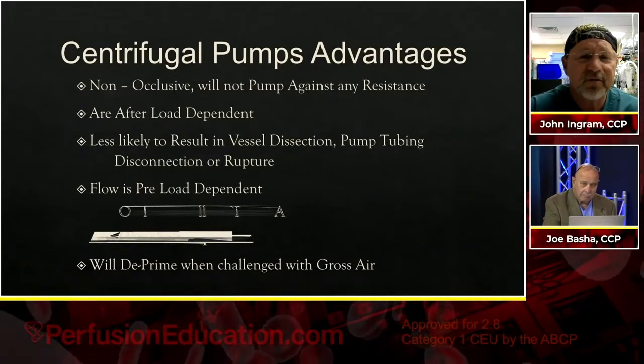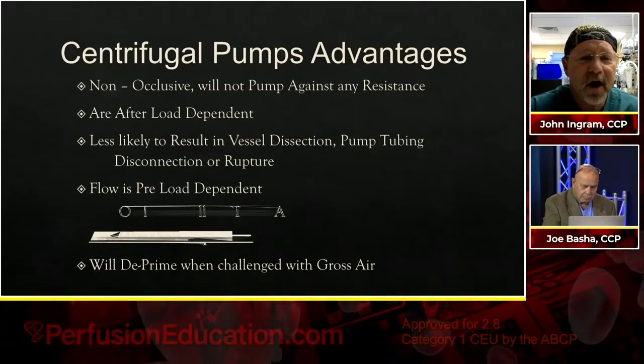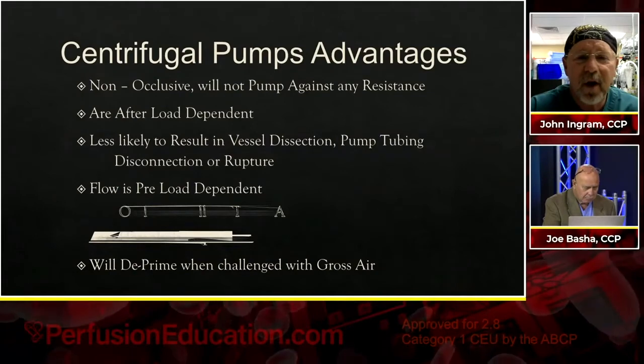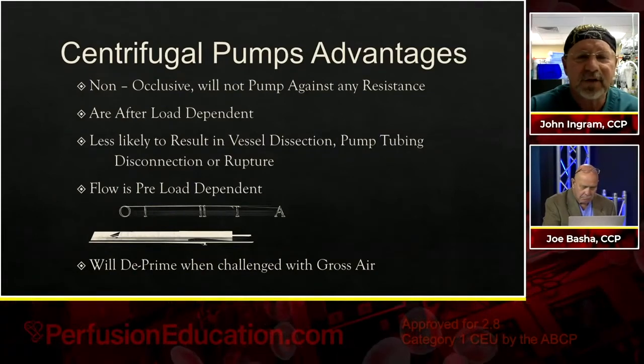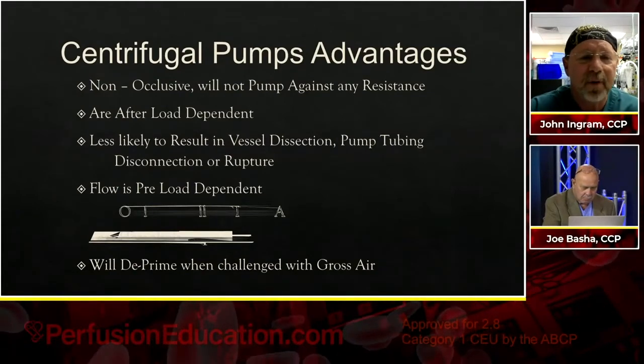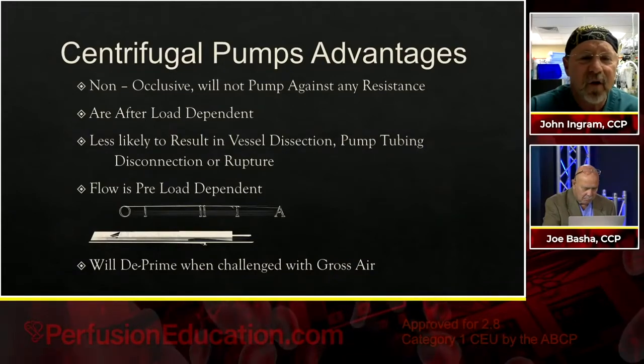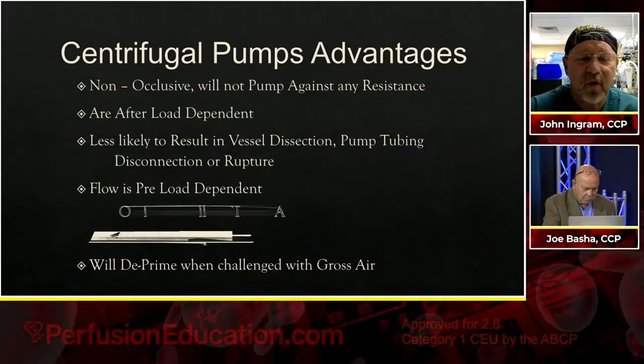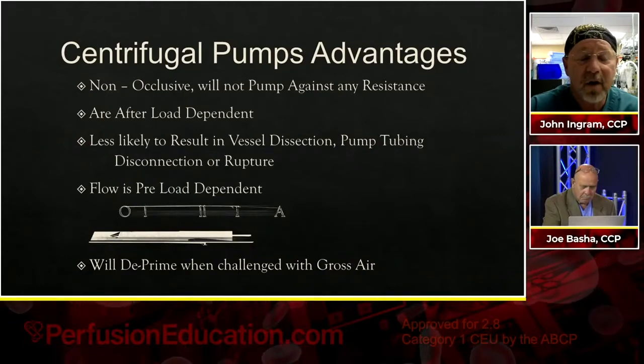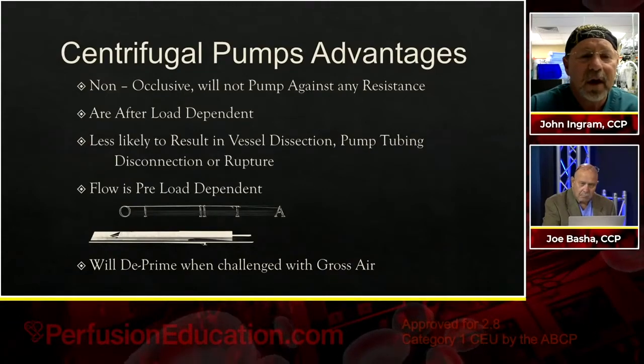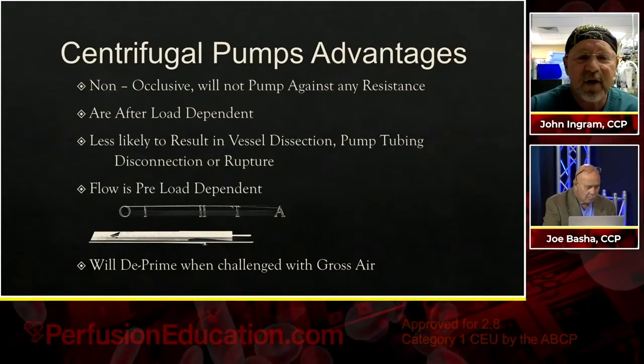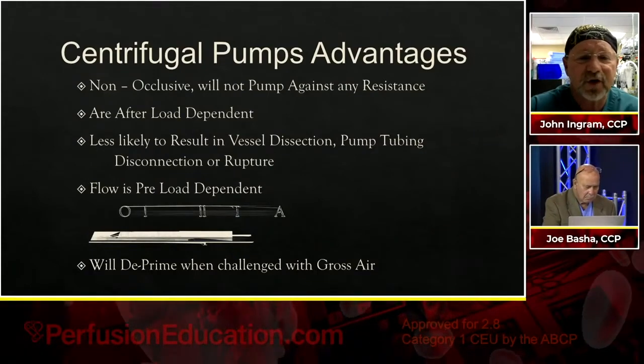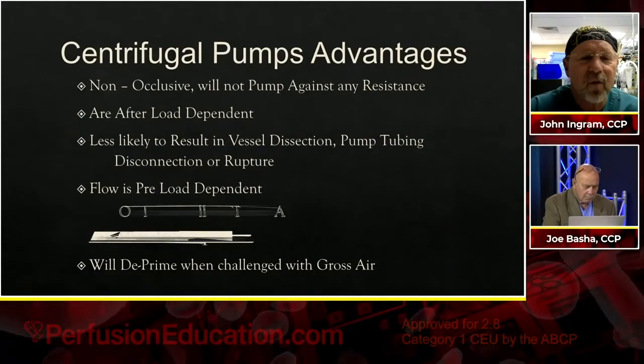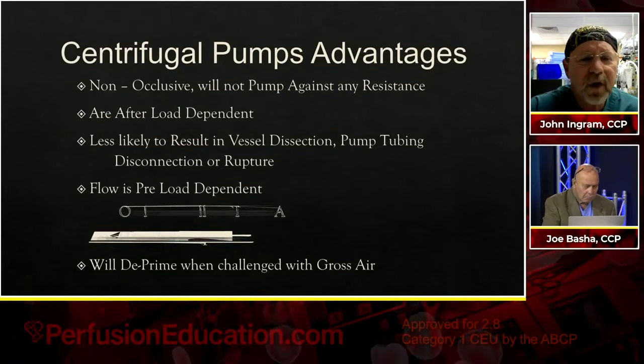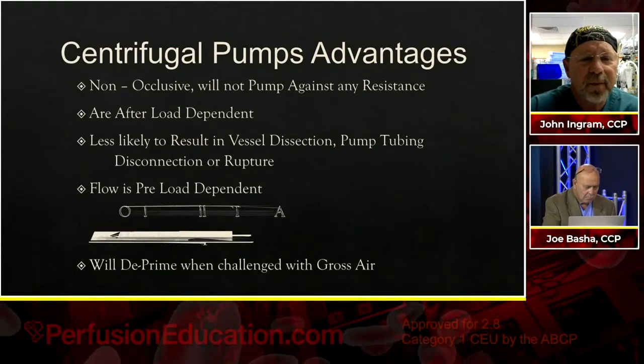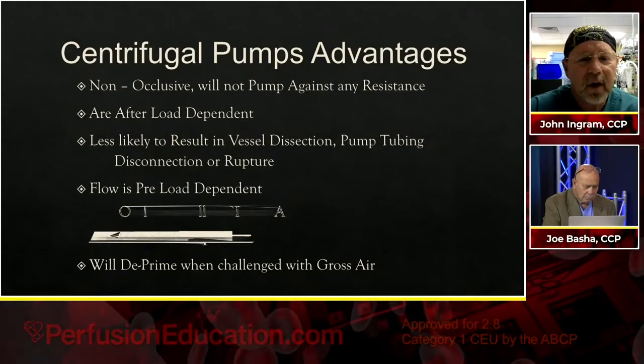Some of the advantages of centrifugal pumps. It's non-occlusive, so it will not pump against any resistance. At a certain resistance, it will no longer continue to pump. It is afterload dependent. You have too high of an afterload, it'll pump either less or nothing at all. It's less likely then to result in vessel dissection, pump tubing disconnection or rupture. That's different than the roller pump model. And the pump is preload dependent.